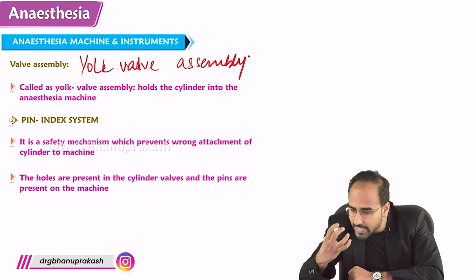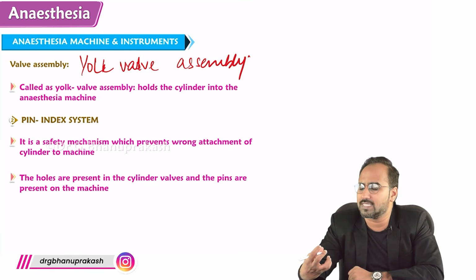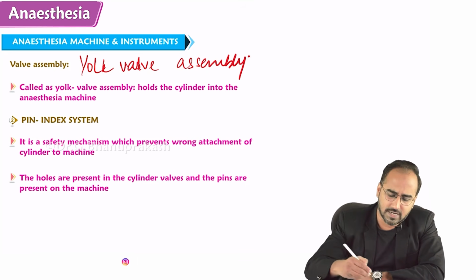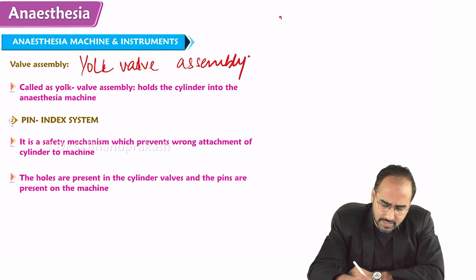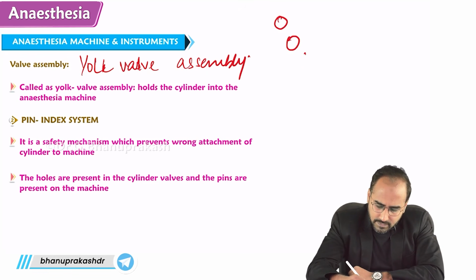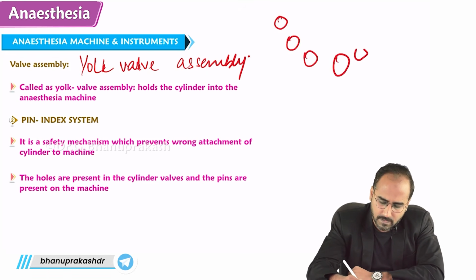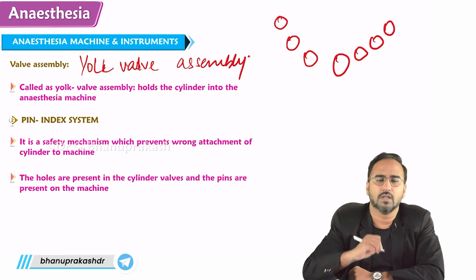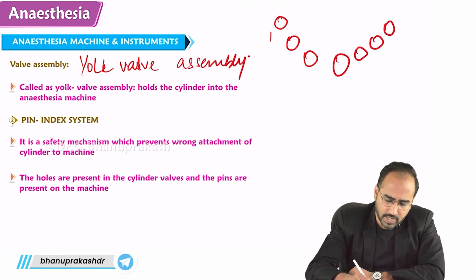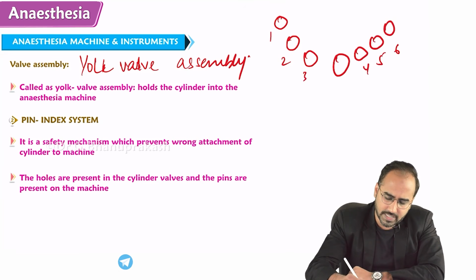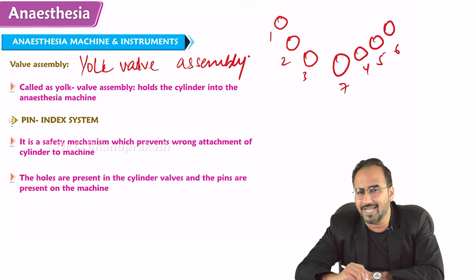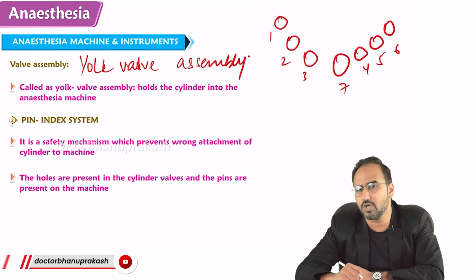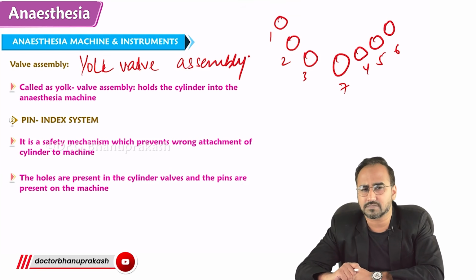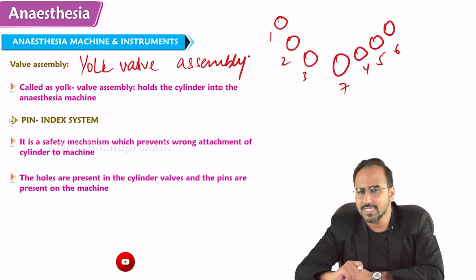On the inner surface of the yoke valve assembly, when you look at the inner surface, you will find these things. We'll just label them 1, 2, 3, 4, 5, 6, 7. What is this? This is called a pin index system. On the inner surface of the yoke valve assembly you see the pin index system. The function of the pin index system is to prevent the wrong attachment of the cylinders.